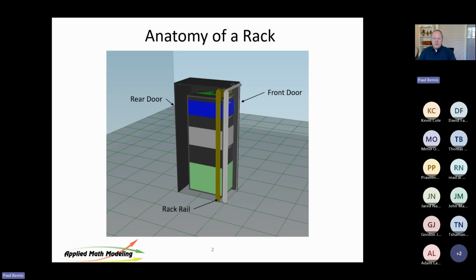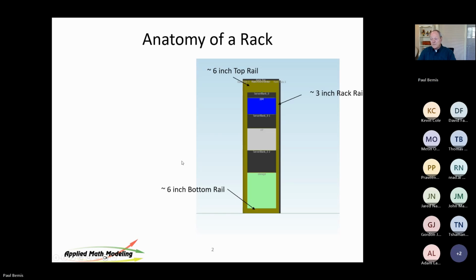Another way to say it is, if you've got a door in the model and you're modeling it and the door's a problem, then that's not a CFD problem. That's an equipment problem. Get the door off it if it's restricting. But the rack rail is important, and that's the one you want to model because it leaks. It leaks on the sides, it leaks on the top, leaks on the bottom. Typically you have 6 inches at the top, sometimes a little less. You have 3 inches on either side, typically. I'm using inches again, I'm sorry. 6 inches at the bottom.